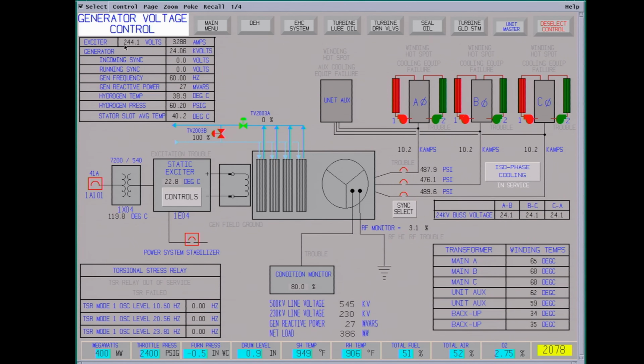Up here we have the exciter. Same thing's running 244 volts, 3298 amps. Generator frequency. This is your breaker, static exciter. Static exciter control. You have a radio frequency monitor. This is looking for harmonics, like arcing in the unit.